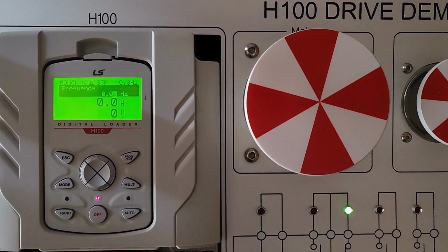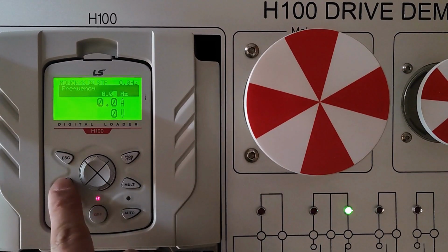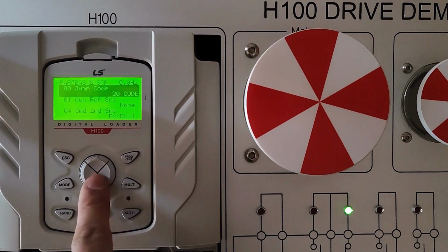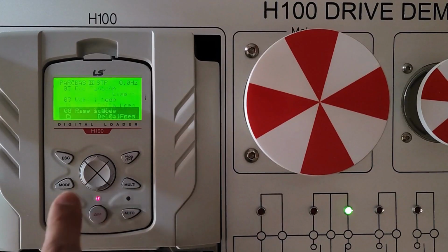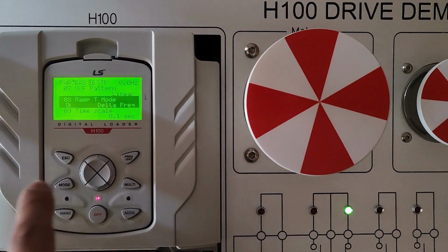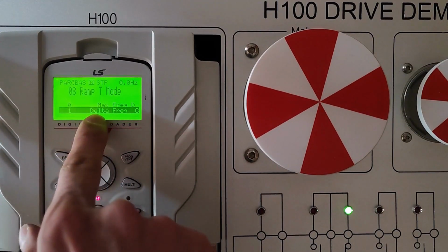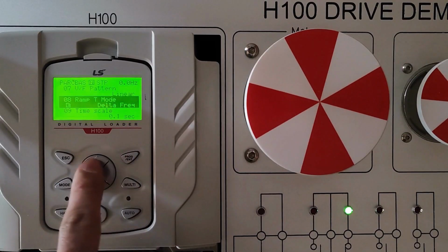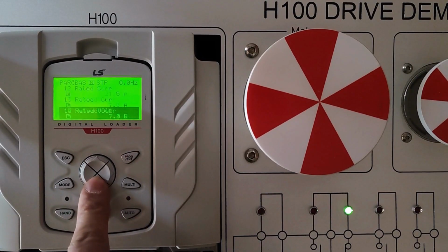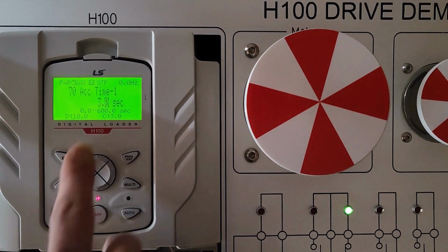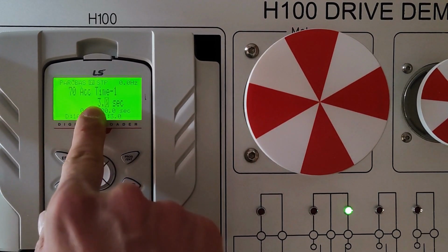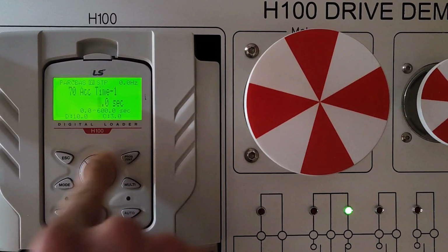So, as we said, in order to use the ACC DEC change frequency feature, the first thing we need to do is go to parameter Base 08 and set our time mode, or the ACC and DEC reference, to the delta mode or option 1. Was it 1? Anyway, as we said, in Base 70 we set our first ACC time. We go to parameter Base 70. We said we want our first ACC time to be 3 seconds, so we set it to 3 and confirm it.